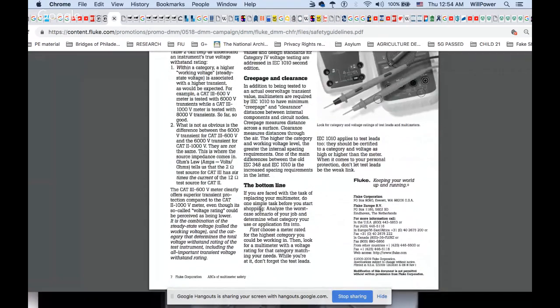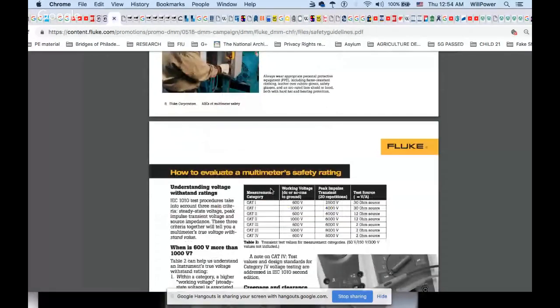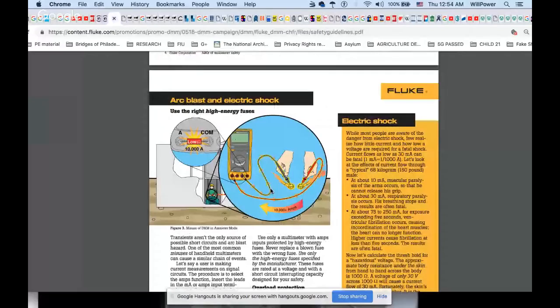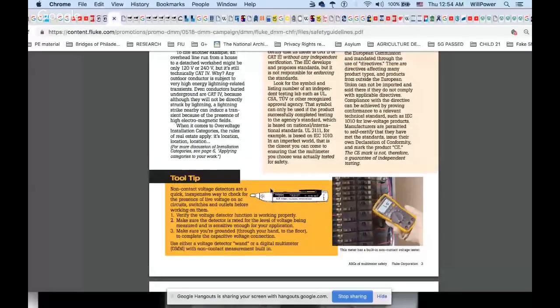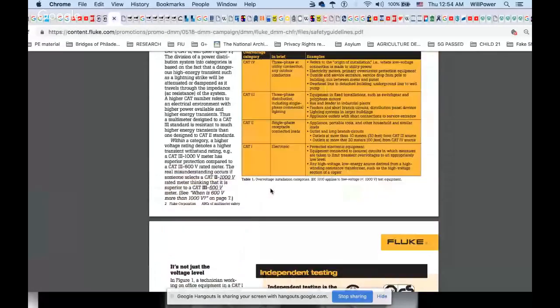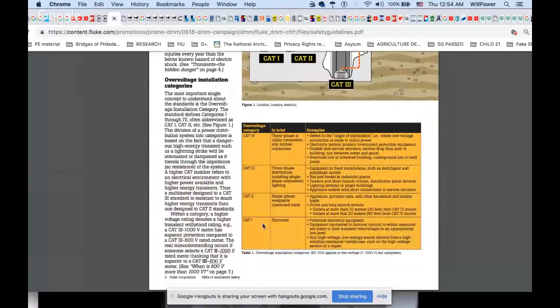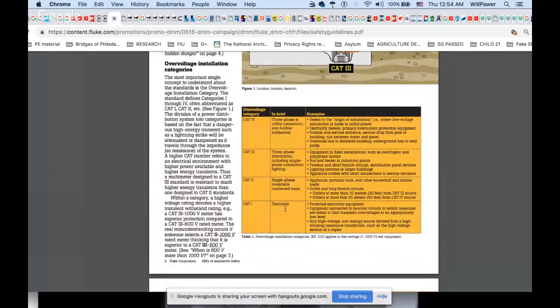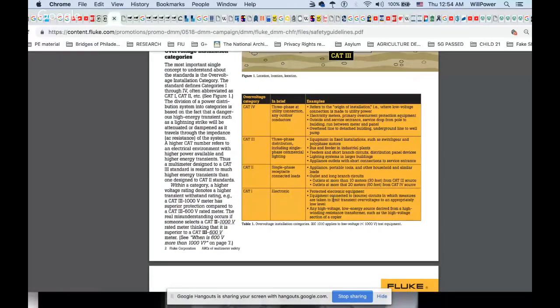Worst case scenario thing, right? All right, let me jump to the top. I'll just give you this link to read. And here's your Cat 1, protected electronic equipment. Equipment connected, so it's already protected, already double insulated stuff. Low energy source derived from high winding resistance transformers, such as the high voltage section of a copier.